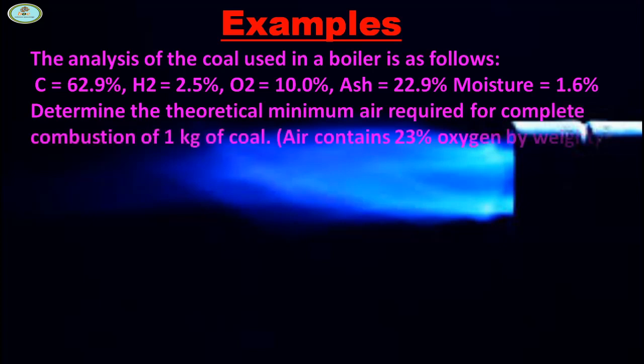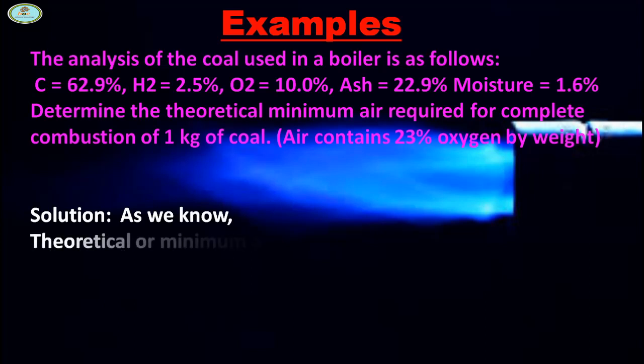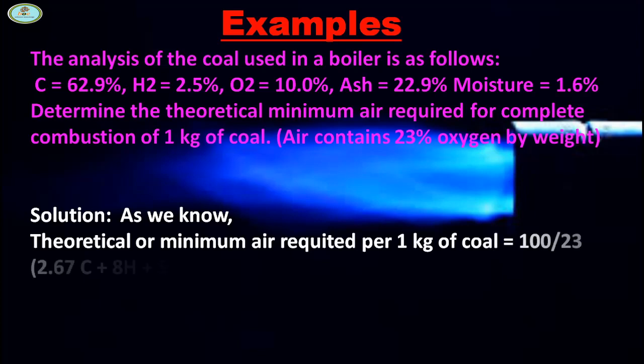Here it contains 23% oxygen by weight. As we know, theoretical or minimum air required for 1 kg of coal is 100/23 × (2.67C + 8H + S - O). Putting all the values, we found 7.74 kg per kg of coal burned.